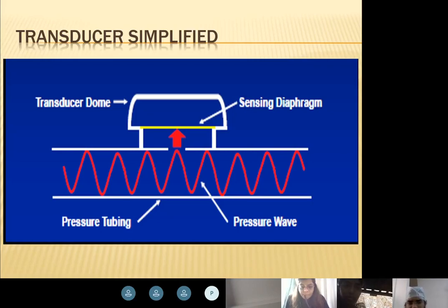So what happens over there is, say for example, on the left side you are attached to the arterial line. From the arterial line a waveform comes, the blood pressure waveform. After all, the blood pressure is 120/80, systolic and diastolic. So you'll have a systolic and a diastolic. Now that wave comes, and the moment it reaches the transducer, it moves this diaphragm up and down. When it moves the diaphragm up and down, that movement is kinetic energy. The pressure that is coming from here is converting into kinetic energy, and that kinetic energy is taken up by the electrical signal, and that gets converted onto the monitor as a waveform or as a number. Clear on this? I'll repeat this once more.